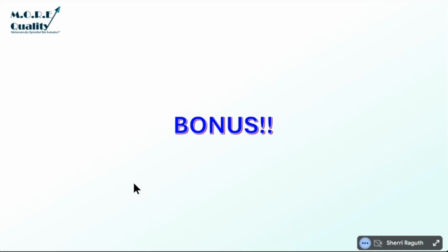Or if I get 3 sigma, that's actually 1.5. So if you go to the Westgard site and look up the error rate associated with 3 sigma, they'll tell you it's 67,000 per million, which is 6.7%, which is definitely not acceptable. You don't want to go to a lab and have a 6.7% error probability.